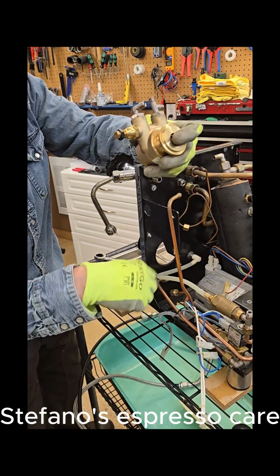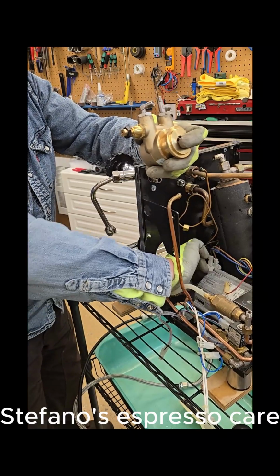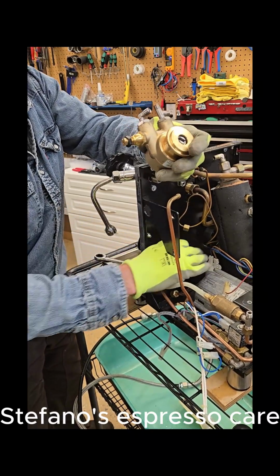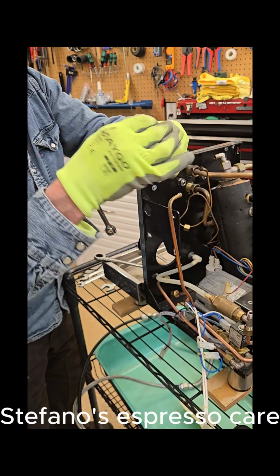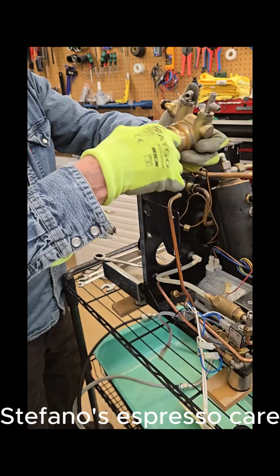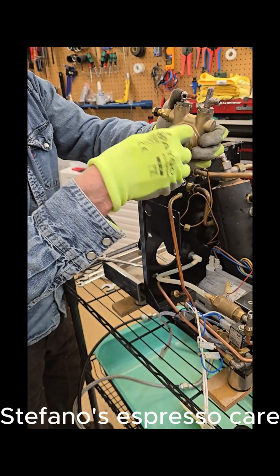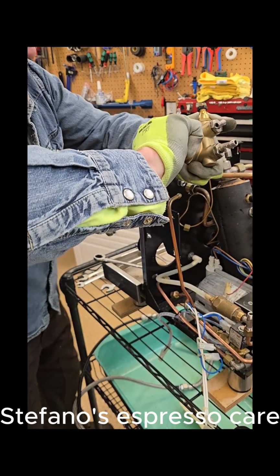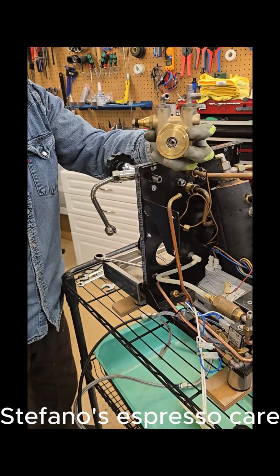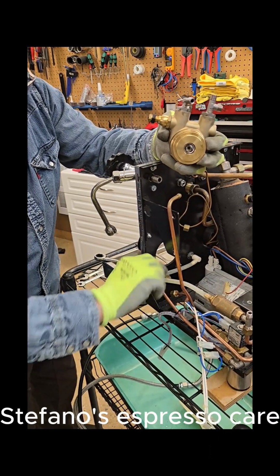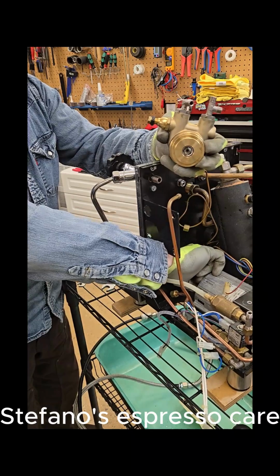The shaft of the pump actually fell in there, so make sure that your pump, when you replace it, has the shaft attached. This pump is indeed almost impossible to move by hand, so that was definitely what was causing the issue on this machine.